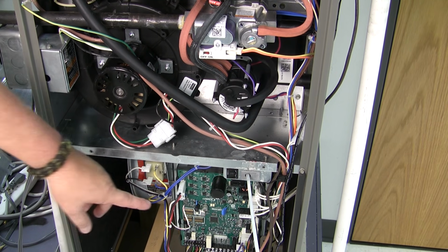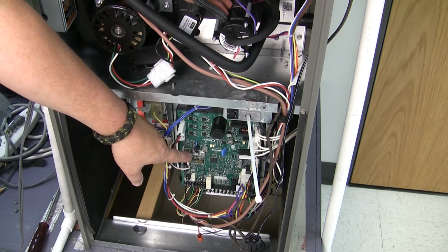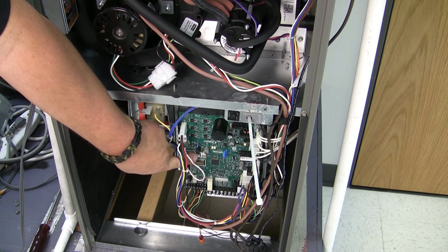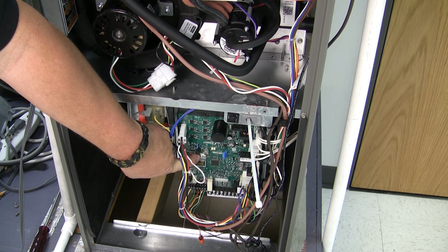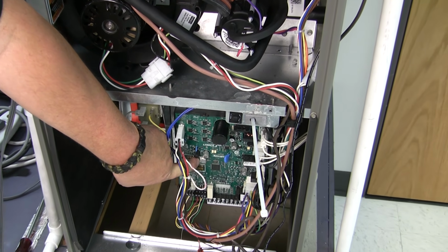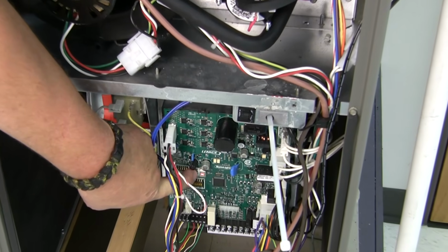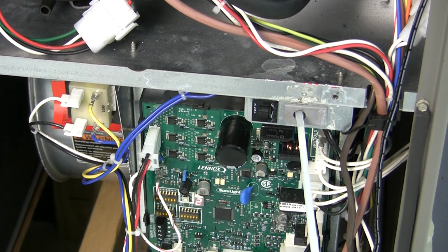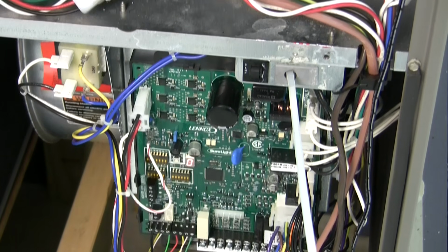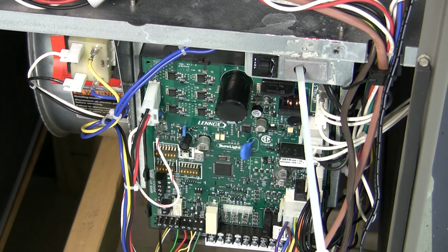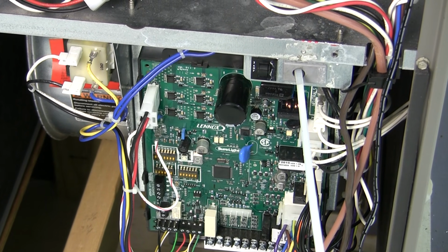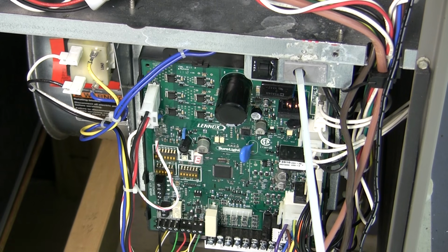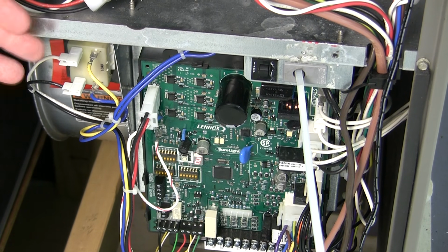and when you get the small pulse, you simply push the white button and hold it until you get an E. Once you get the E, you release, and then it will start running through the fault codes again. And then you simply record them and then refer to the chart to figure out what the fault codes are.